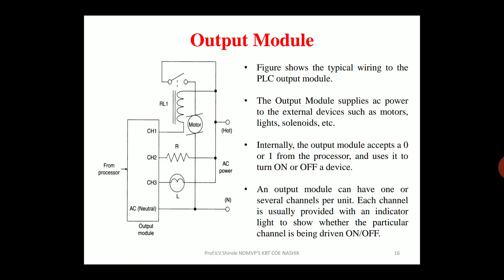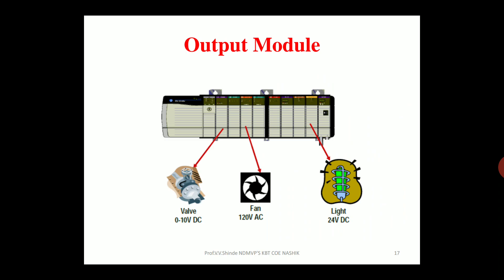Similar to the input module, there is also an output module. The output module supplies AC power to external devices such as motors, lights, fans, solenoids, etc. Internally, the output module accepts a 0 or 1 signal from the processor and uses it to turn on or off the device. An output module can have one or several channels per unit, and each channel is usually provided with an indicator light to show whether that particular channel is being driven on or off.